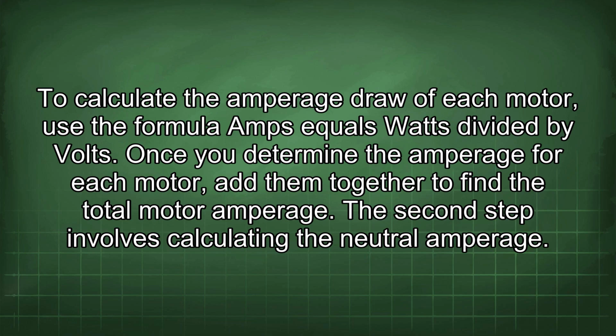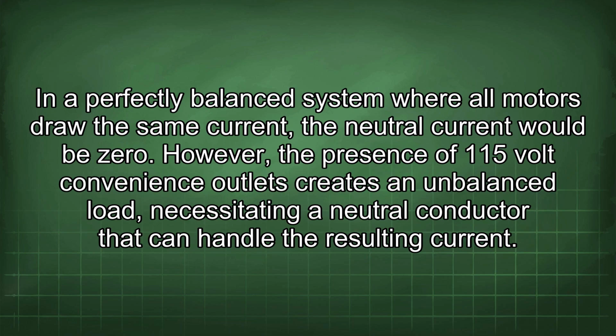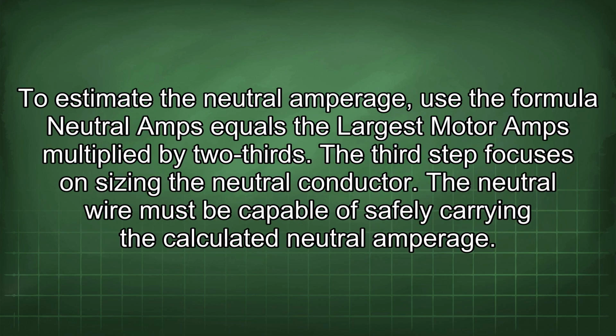The second step involves calculating the neutral amperage. In a perfectly balanced system where all motors draw the same current, the neutral current would be zero. However, the presence of 115-volt convenience outlets creates an unbalanced load, necessitating a neutral conductor that can handle the resulting current. To estimate the neutral amperage, use the formula neutral amps equals the largest motor amps multiplied by 2/3.